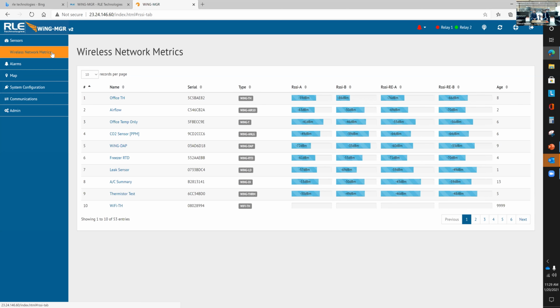That's one that I think you guys are going to like a lot. Right now we have it set up with our analog transmitter - so it's a CO2 sensor, wall input, wall plugged or powered, however you're going to do that. It could be a duct sensor. What we're doing is taking the 0 to 10 volt output into our analog transmitter and transmitting these radio signals every 10 to 20 seconds. So if I haven't said it already, our radios talk every 10 to 20 seconds in a random fashion to make sure you can see them all changing age of data on the right-hand side.